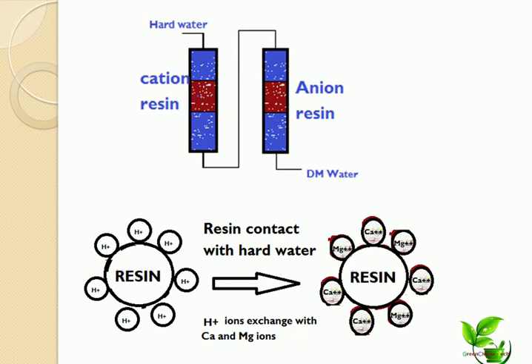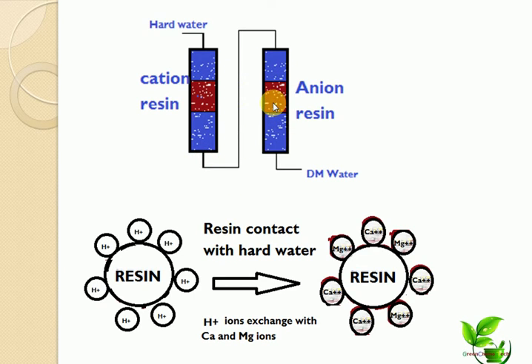In the process diagram, hard water passes first through the cationic exchange resin, where all cations are absorbed. The cation-free water, containing hydrochloric acid and sulfuric acid, then passes through the anionic resin, which absorbs all anions. The resulting water, free from both cations and anions, is called demineralized water.